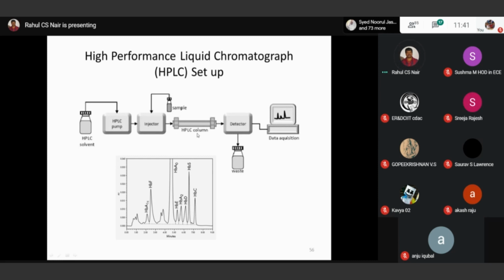So the separation occurs on the HPLC column. This column is packed with different materials, maybe silica or something of that kind, where the separation occurs. Depending upon the particle sizes, these are bonded to different parts of this column packing. Finally, they are eluted by pumping out a buffer solution, and the detector detects and provides a peak. You can see a diagram of this.